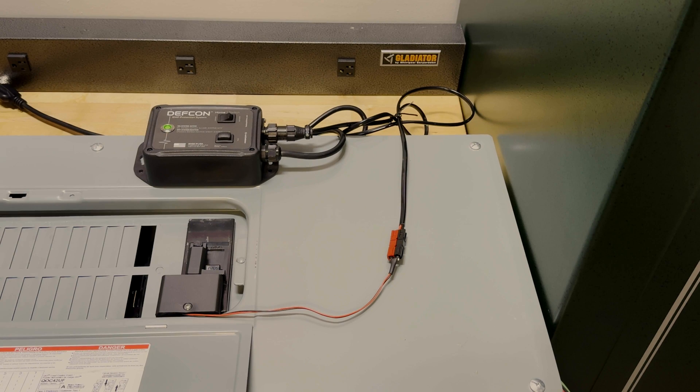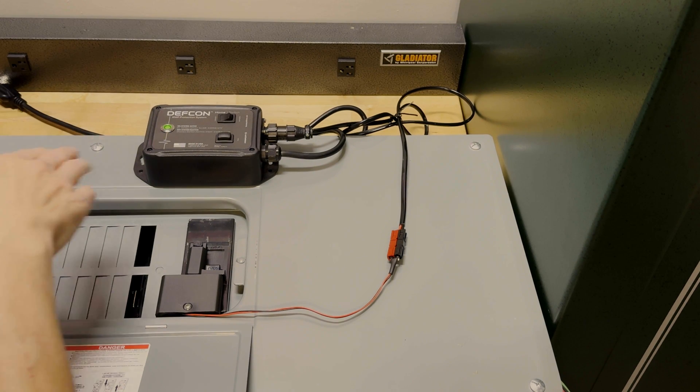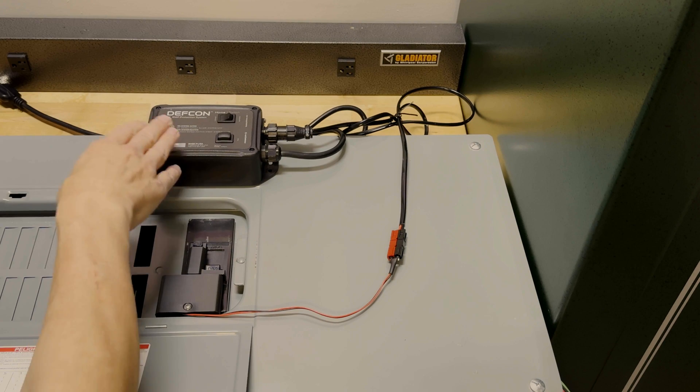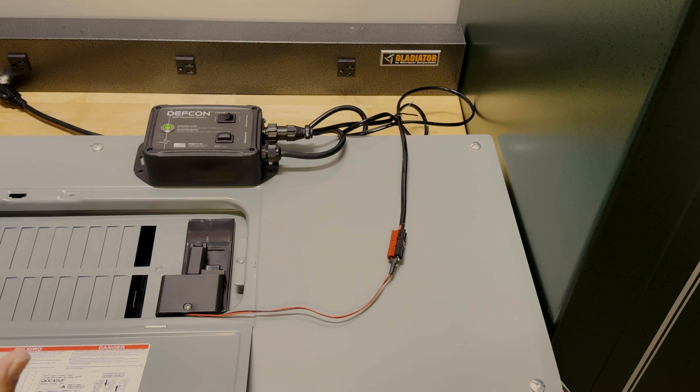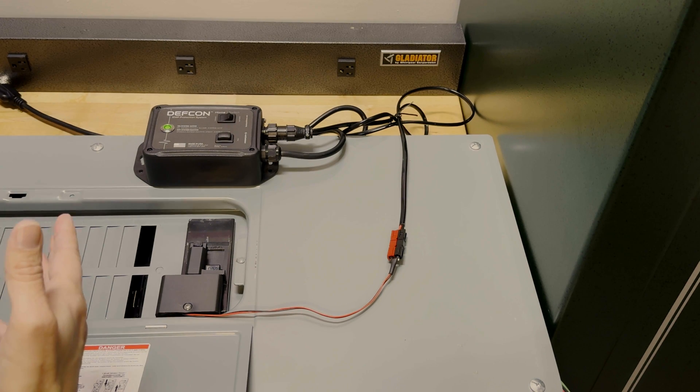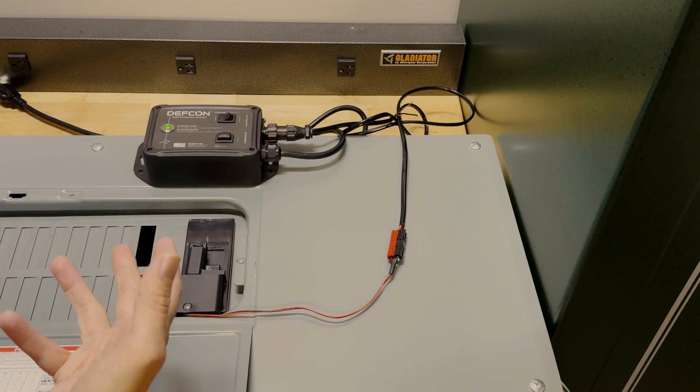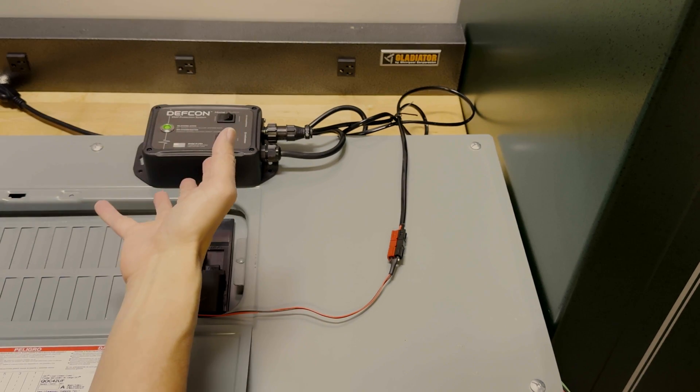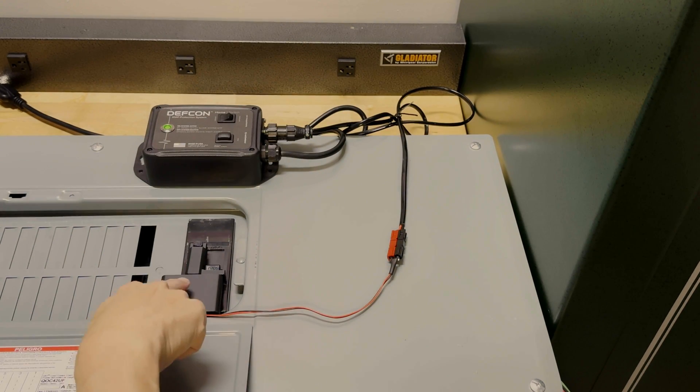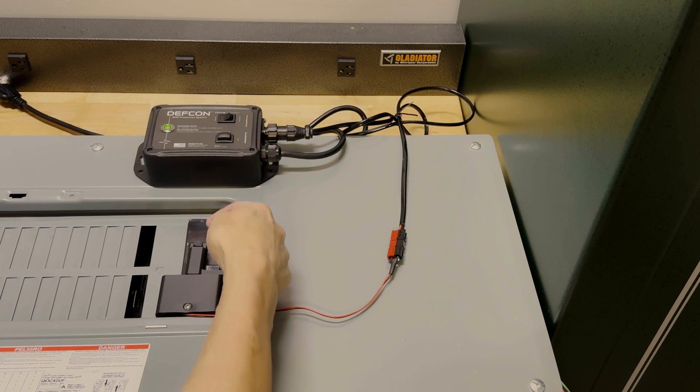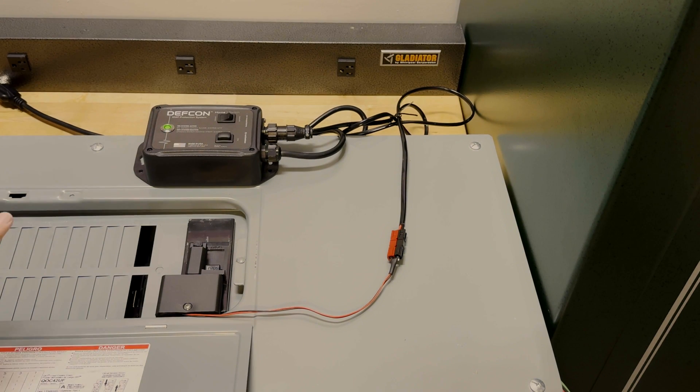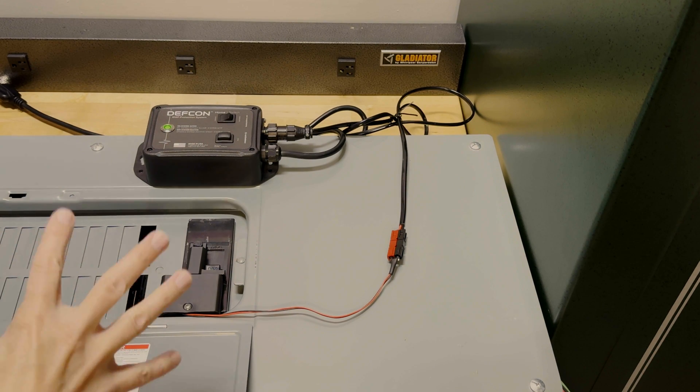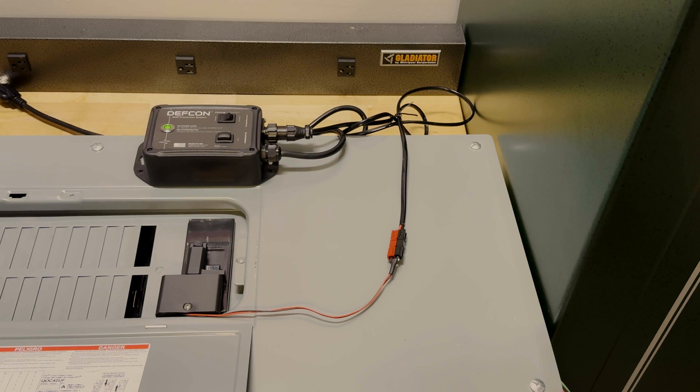So let's discuss how the system actually works. When I plug the unit in, you'll see the green light light which indicates AC power is applied and then the unit goes into a detection mode. It will now be looking for the radiated pulse from an EMP, that is the E1-E2 pulse. If it sees such a pulse come in, it will drive a signal over to the actuator assembly which will then trip the breaker. That disconnects your home or business from the power lines which is where a lot of the damaging energy can come in over time. So you're trying to disconnect very early in the EMP cycle.